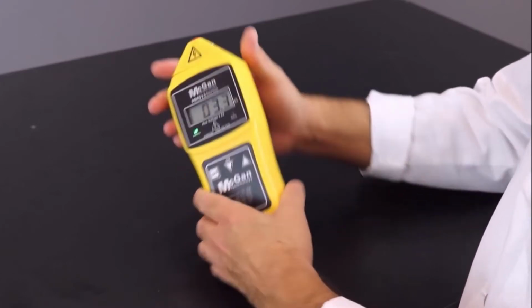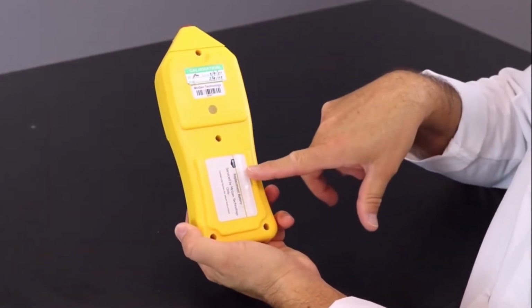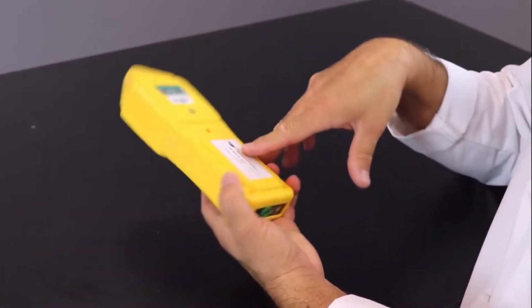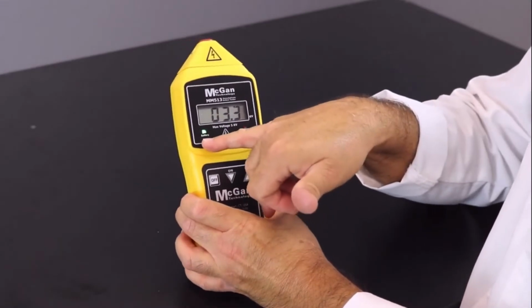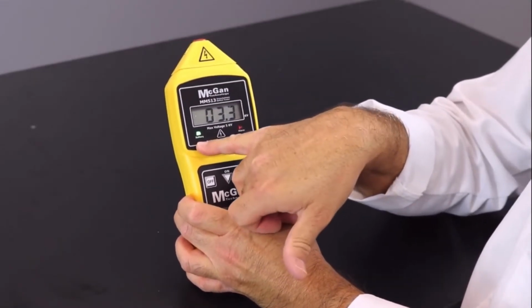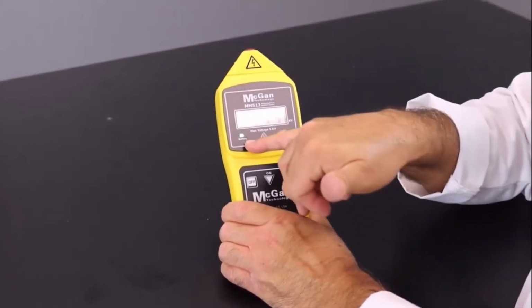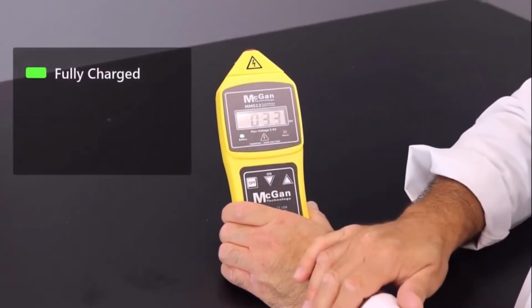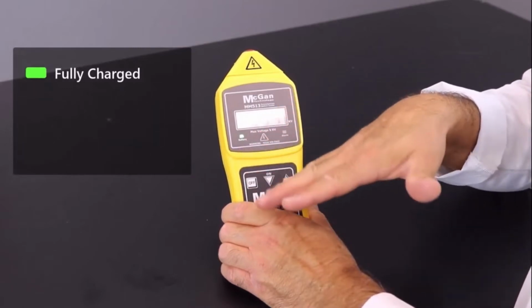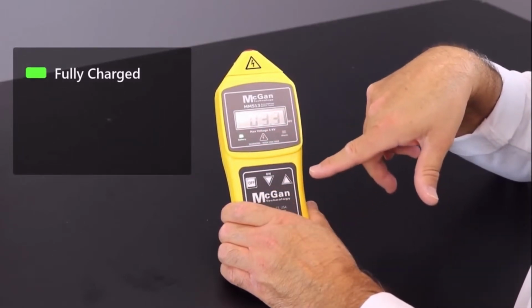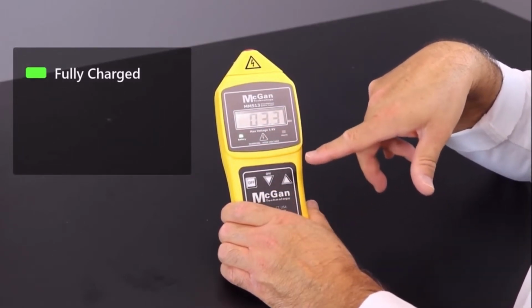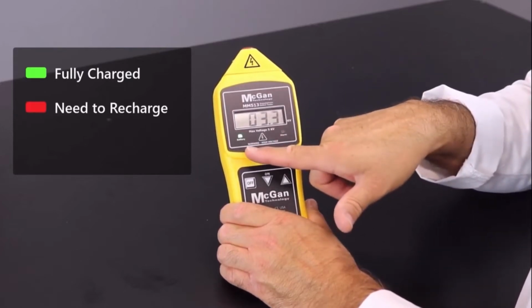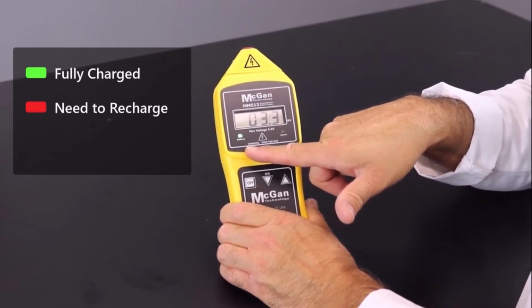The unit has a rechargeable lithium polymer battery and has a battery LED indicator light that's on the left below the display, stated here, battery. For our US model, if the battery light is green, the battery is fully charged and can operate around 10 hours or up to 1,000 instruments. It can take 2 to 4 hours to fully charge. If the battery light is red, the battery is flat and you will need to recharge the unit.